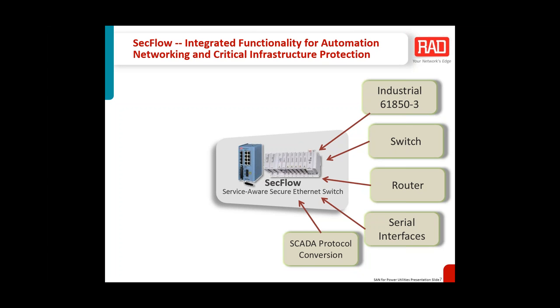Here in North America, that's primarily DNP, though we do see some Modbus, and occasionally you'll see the IEC 104 protocol used. But typically it's DNP, with DNP3 being the most current version, though some utilities support Modbus.